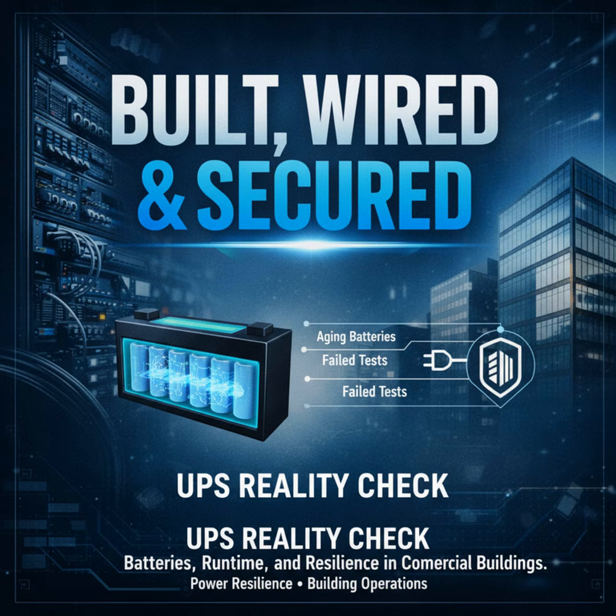Segment 3. Operational implications. Michael, walk us through maintenance cadence, documentation handoffs, and vendor oversight in a way that facilities and IT can act on. Start with an owner's checklist. At minimum, an annual full load or representative load discharge test, quarterly health checks that record capacity and internal temperatures, and clear battery replacement triggers tied to capacity thresholds, not just years in service. Second, require vendors to provide trend logs and a failure mode report after each service visit.